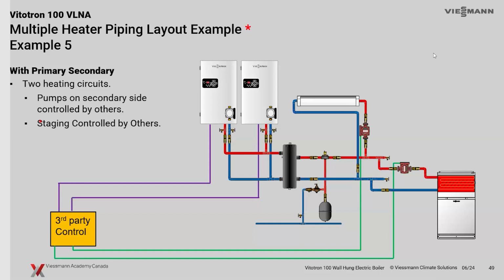And essentially, we're just doing an enable-disable contact on these. So it's essentially just a straight on-off contact. We're not doing 0 to 10 or any type of 4 to 20 milliamp. We're going to essentially just stage these based on a dry contact from the control back to the individual boilers that we're looking at.